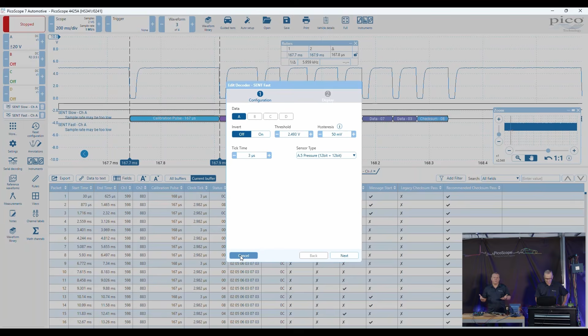I always say, expect what you inspect. You do need to know what you're doing. You need to know what type of sensor you're measuring, because in the decoder, you need to add that. You can make those changes if you need to. I've looked at quite a few of these now, and I have never seen anything other than 3 as a tick time, so it seems to be fairly standard. I'm glad you said that, because you could be presented with numerous errors and blame your measurement technique, your configuration, your setup, till proved otherwise. So whilst the guided test helps you out and gets you off and running, you will need to make amendments for the type of sensor you're working on.